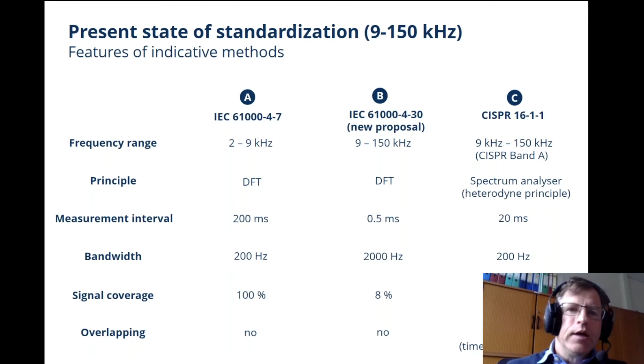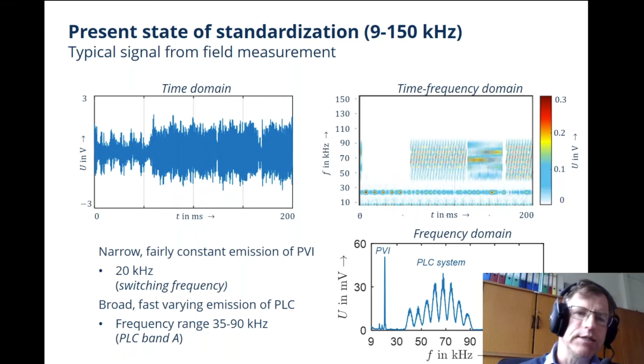So let's see how these three methods compare for a typical signal from the field. This is a signal we measured in an installation of a PV inverter combined with a narrowband power line communication system in Austria. In the lower right figure, in the frequency domain, you can see two distinctive emissions up to 150 kilohertz: the PV emission at 20 kilohertz, which is narrow and fairly constant over time, and the power line communication system, which ranges between 35 and 90 kilohertz. It has typically 8 channels for transmission, which is definitely broad relative to the frequency band we analyze, and it varies pretty fast and significantly.